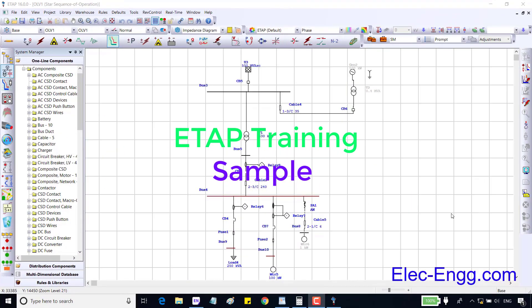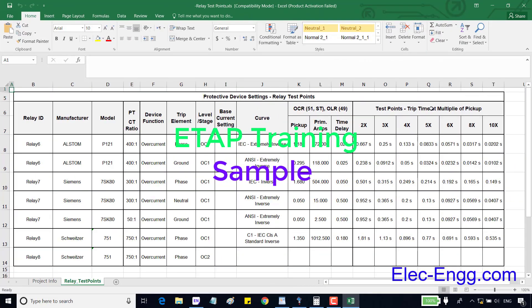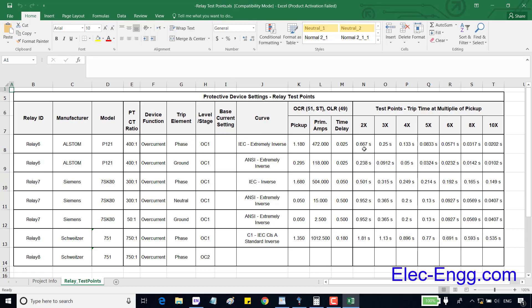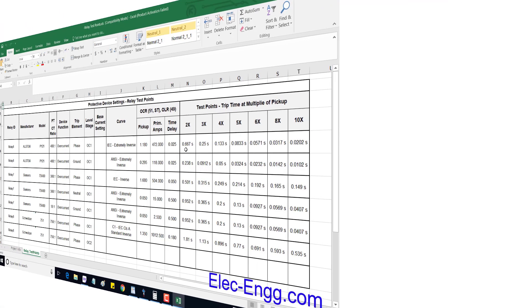In this session we are going to overview the protection tab in each element. Here each relay has some test points and time in seconds. For example to test this relay, relay 6 which is a P121, if we take two times the pickup current, the relay should trip at 0.667 seconds. In a real test we would inject the pickup current to this value.